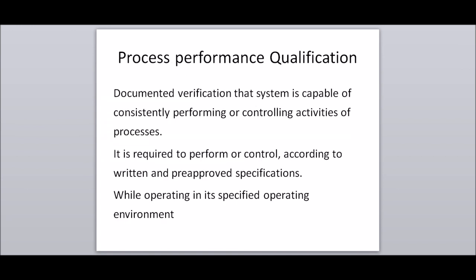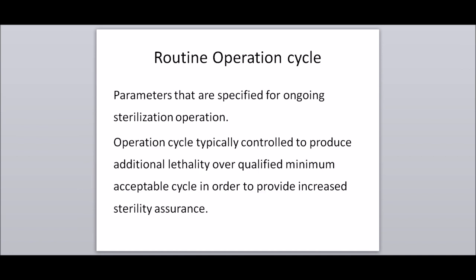Process performance qualification: documented verification that a system is capable of consistently performing or controlling the activities of the processes, according to written and pre-approved specifications while operating in its specified environment. Routine operation cycle: the parameters specified for ongoing sterilization operation, typically controlled to produce additional lethality over the qualified minimum acceptable cycle, in order to provide increased sterility assurance.